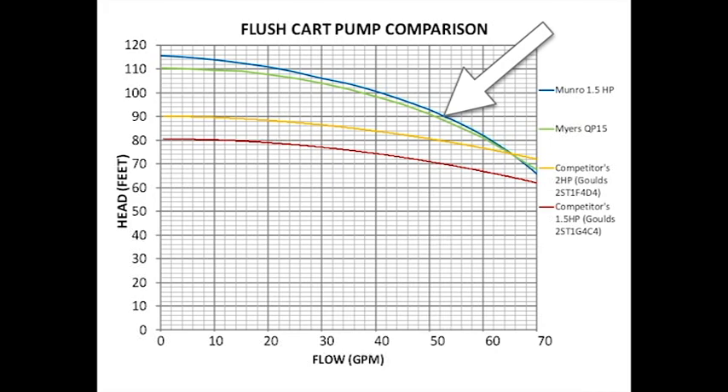As you can see from the graph, the Munro pump has the highest head on the market, allowing the flush cart to purge air from most loops up to 10 to 12 three-quarter inch circuits, if designed with reducing headers. Consult the online flushing calculator for your particular design.